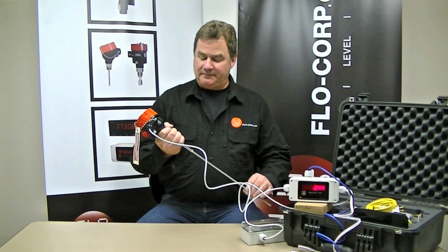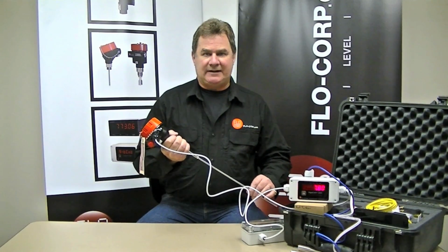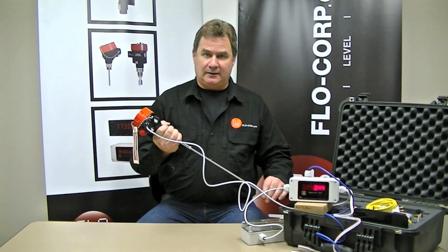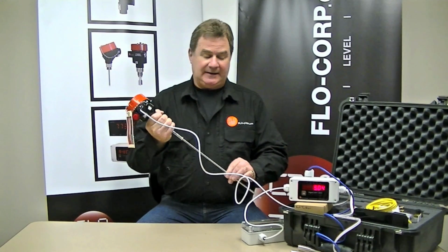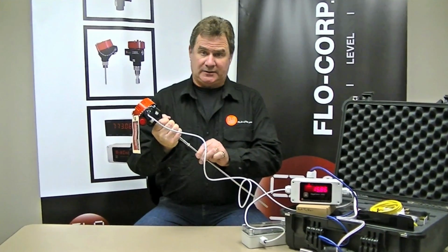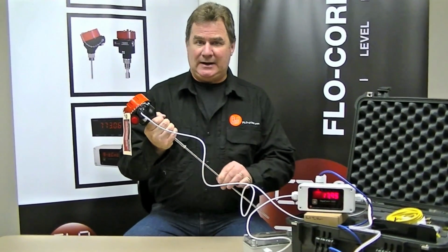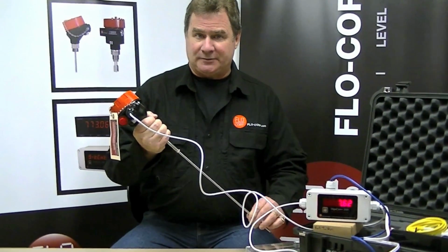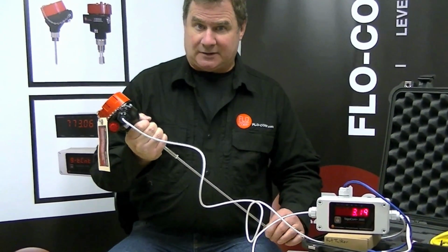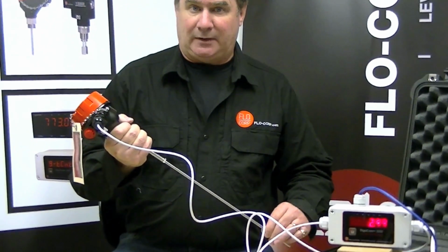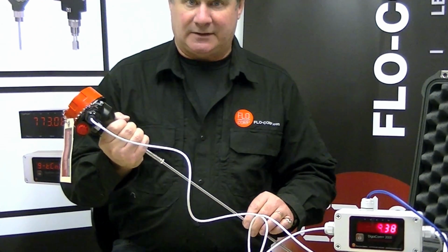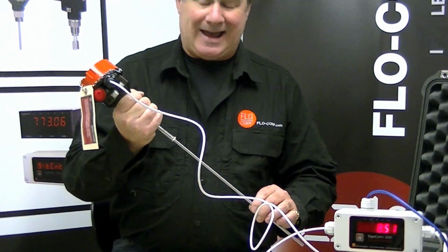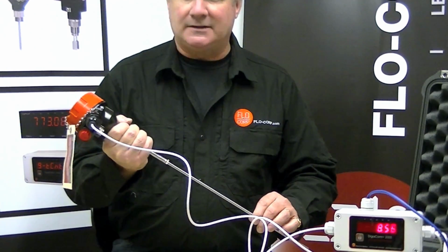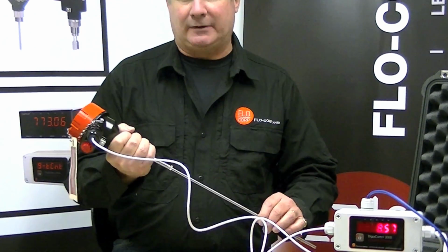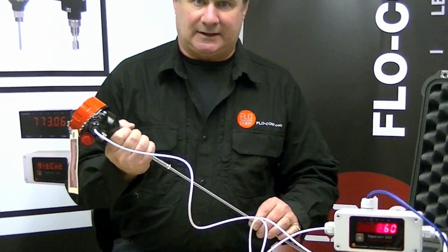The tracer level transmitter takes 70 samples per second. Therefore, as you could see, the level response, or the response to level change, is immediate. The 70 samples per second also gives our customer better than a 1 millimeter resolution and accuracy. So it's an extremely accurate, very fast speed of response, and highly reliable level measuring signal.